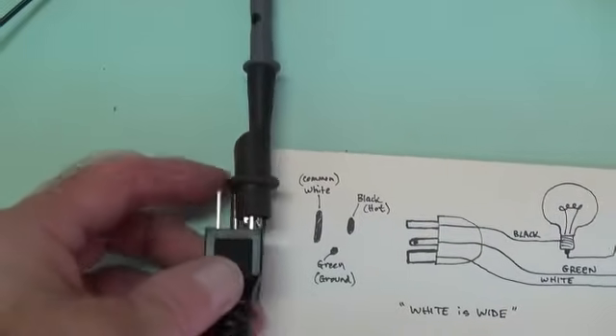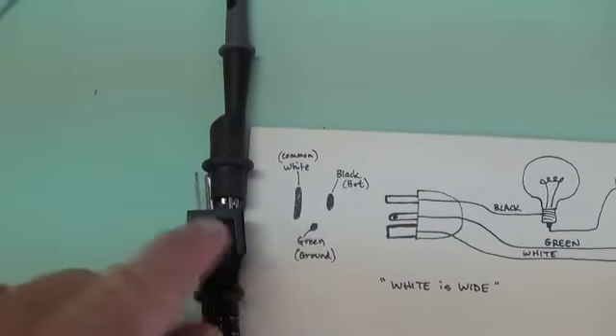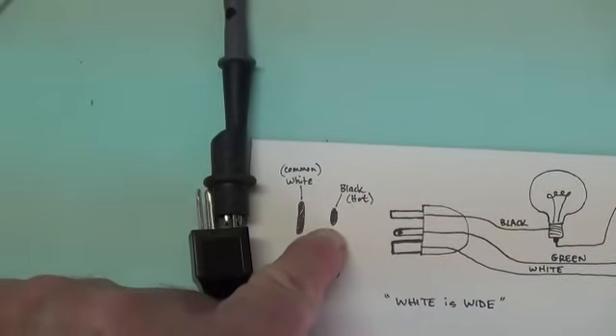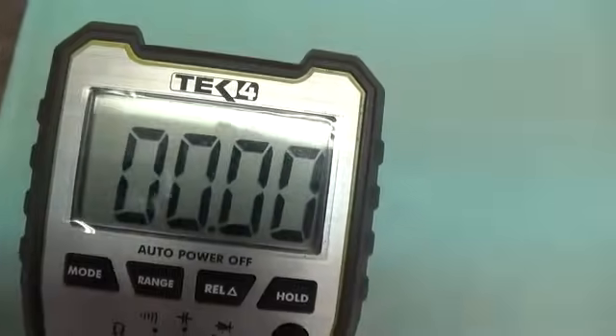I have the ground lug at the bottom, like in the drawing, and the right-hand blade should be black, which is hot. I've gone over here to the black wire, and as you can see, there are zero ohms. There is continuity.